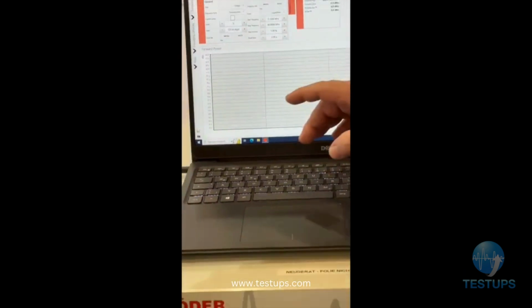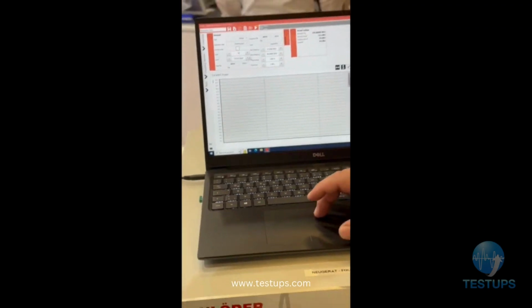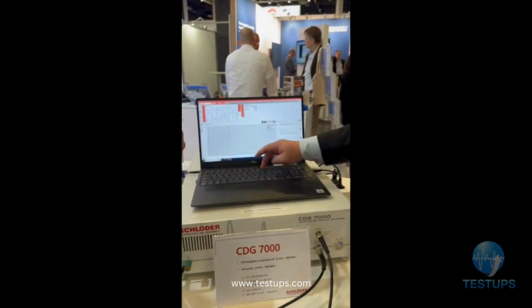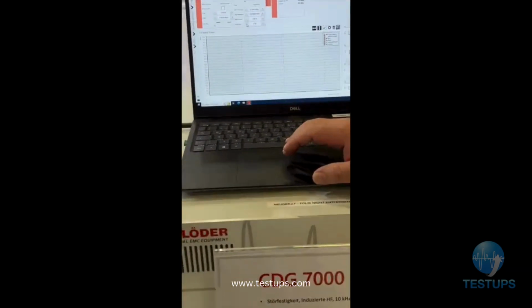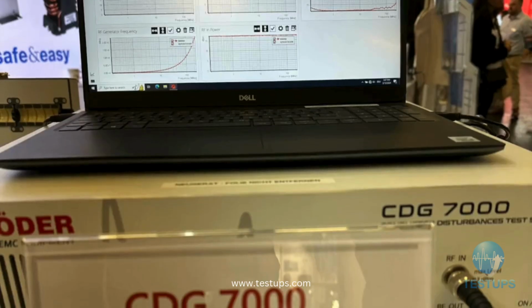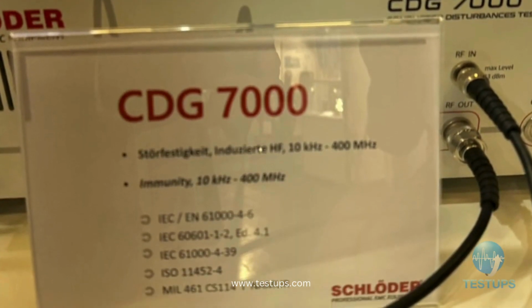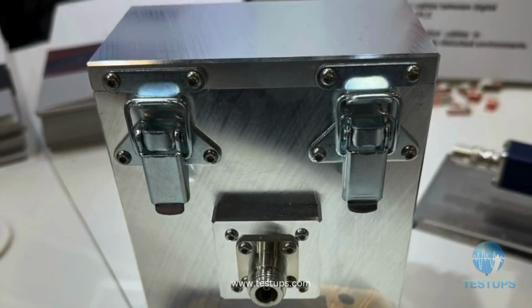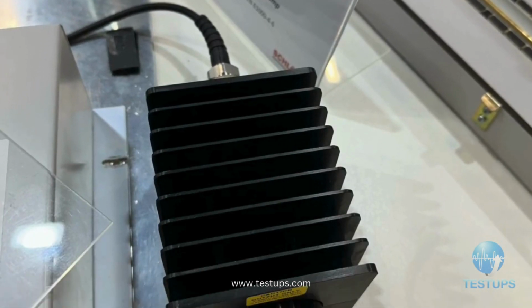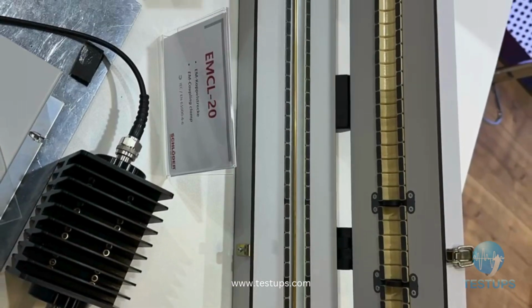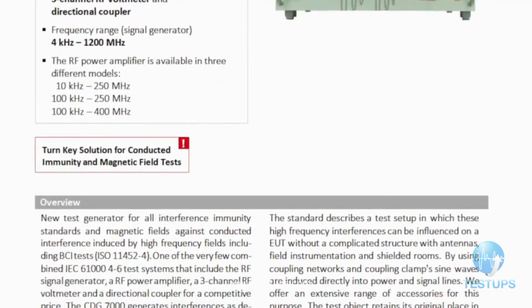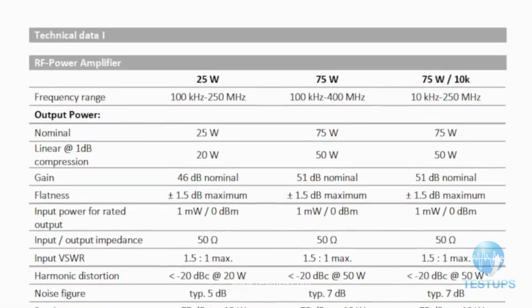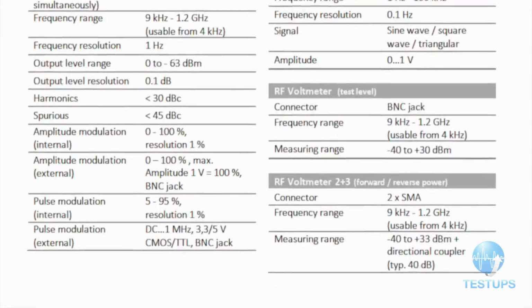And I see that the CDG 7000 comes with a whole set of accessories specifically for calibration. Can you walk us through what those are and how they're used? Sure. The calibration accessories include things like attenuators, terminations, and special cables and connectors. Attenuators are used to reduce the signal strength in a controlled way. And terminations absorb signals to prevent reflections that could interfere with the calibration process. So it's like fine-tuning the system to make sure it's operating at peak precision.